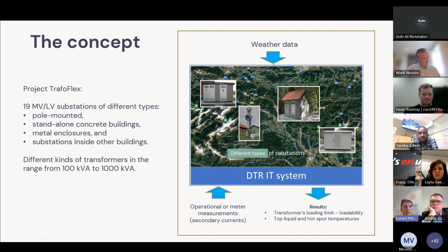And we have two main inputs to the system. The first one is weather data, and the second one is operation or meter measurements. We measured the secondary currents. And the result of the calculation was the transformers' loading limit, loadability, top liquid, and hotspot temperatures. Proceeding to the next slide.